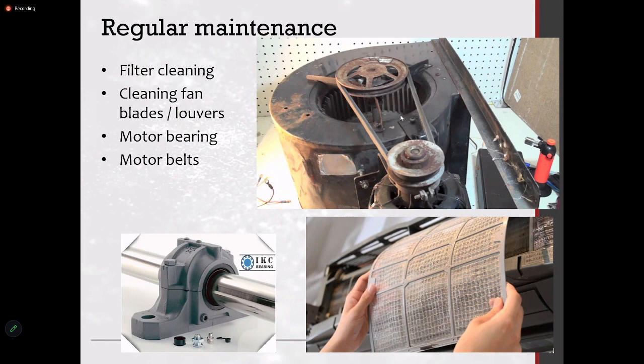So to ensure the humidity is reduced, you have to ensure proper air circulation. At what intervals the filter cleaning has to happen is very difficult to judge. It depends on the space you are in, and it depends on how much your air is polluted. So if you are in a city area or in a congested area, then the filter cleaning will have to happen frequently. Otherwise, indoors also you get the same fins which are available just like the outdoor. So if the indoor fins get clogged, then the proper heat transfer will not happen.